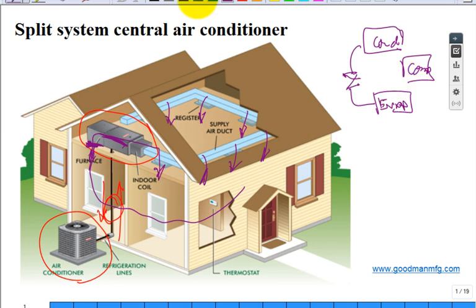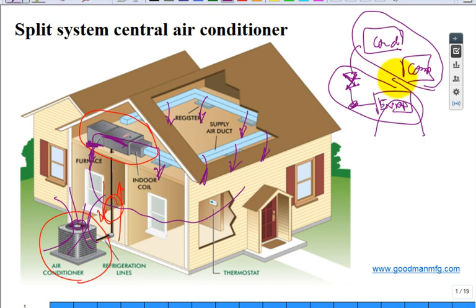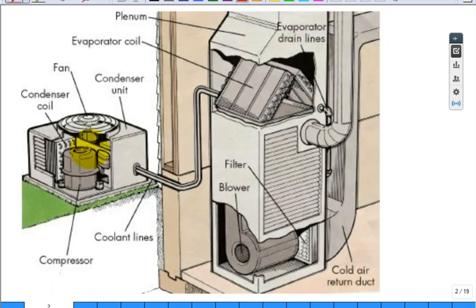So what's on the outside of the house? The outside of the house has the compressor and the condenser coil and the air is brought over the condenser coil and then the air fan brings it across and shoots it up like that. That's how it's rejecting heat to the outdoor air in the hot summer day. We already talked about the indoor air is passed over the evaporator coil and because the expansion valve, as soon as it expands, it's cold. You keep it really close to the evaporator. The expansion valve is right there, close to the evaporator.